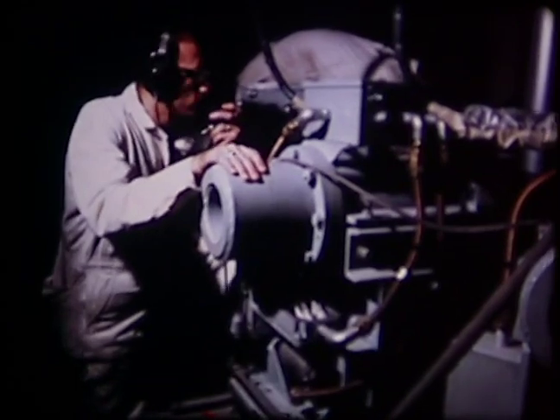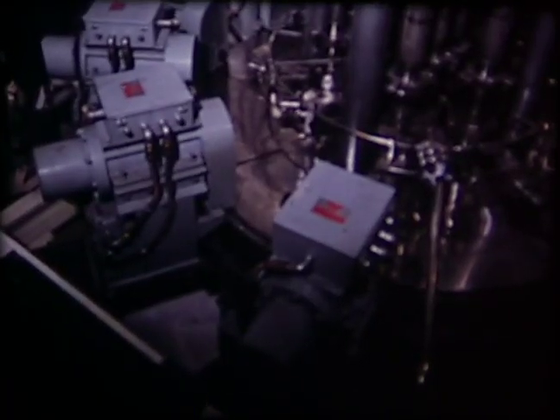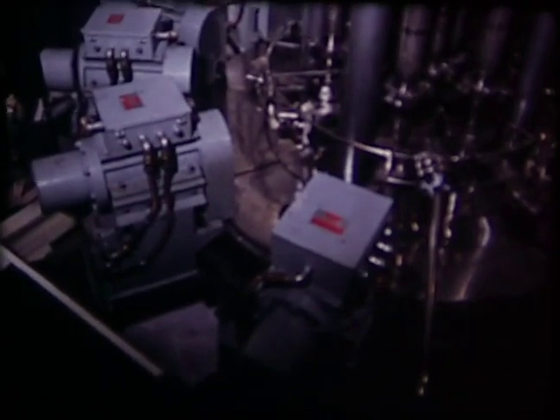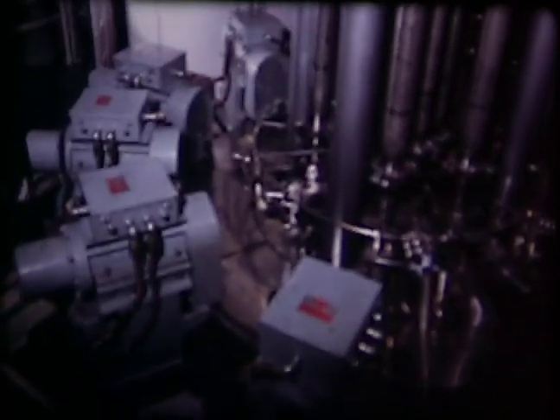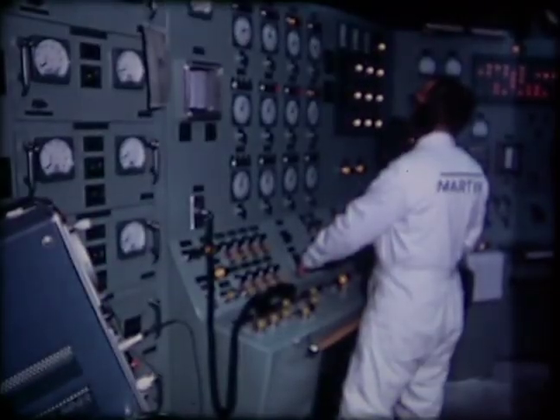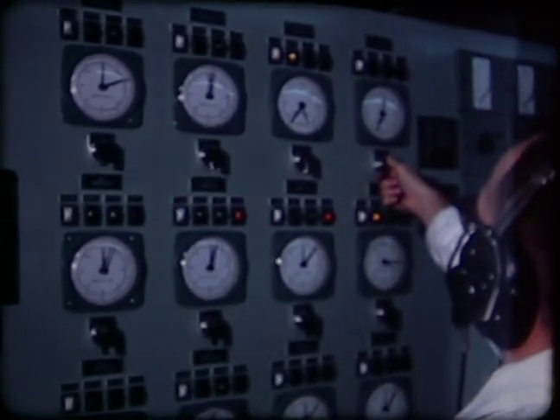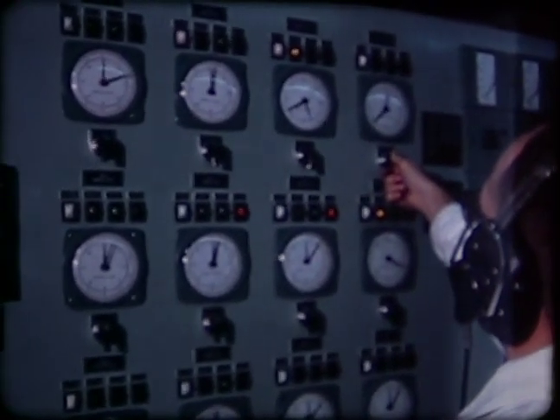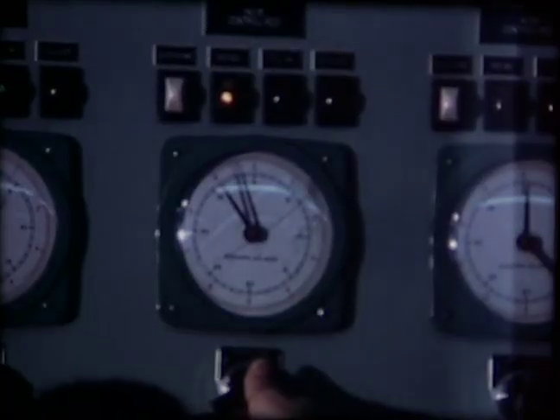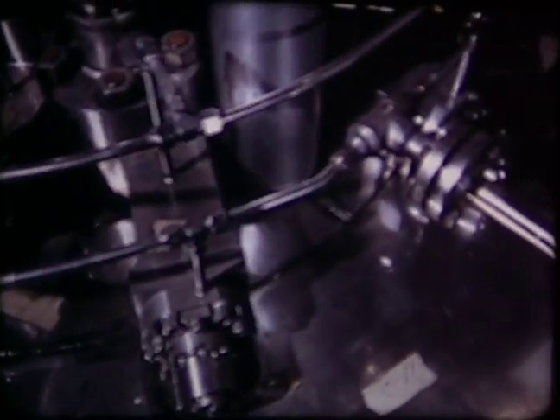These 12 actuators drive the control rods to the fully inserted position at 2 inches per minute in normal operation. At a scram, a minimum of 8 inches of travel occurs within 1/2 second. The actuators are operated automatically under scram conditions. Thus, the reactor will be rendered subcritical even in the unlikely event of capsizing. This feature has been tested with the actuators in the inverted position. A buffer seal system controls the coolant leakage through the actuator dynamic seal.